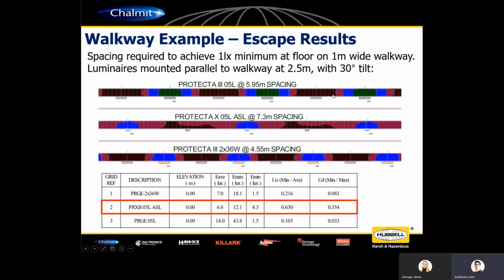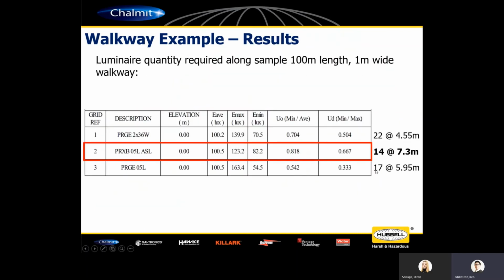Just an extra bit of information here, to show you that same walkway in emergency mode. In emergency or escape conditions, typically you want to achieve 1 lux minimum along the walkway itself. What I can confirm is that irrespective of whether it's Protecta GRP, Protecta fluorescent, Protecta LED or Protecta X, you still need every second luminaire to be an emergency product. But that's still significant in terms of your overall quantities.